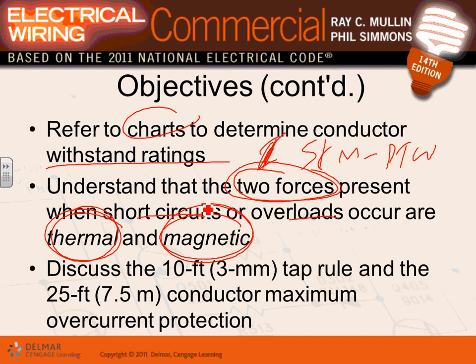Oh boy. So that's exactly like shake and bake. Your panel is being shaken, physically, mechanically shaken by the magnetic force, and baked by the heat generated by the short circuit. Now, what's worse than that? If you have a short circuit in your power system, every single component that is part of the short circuit will be shaken and baked. For how long? As long as it takes the circuit breaker or the fuse to open. You have shaking and baking happening as long as the circuit breaker takes to open.